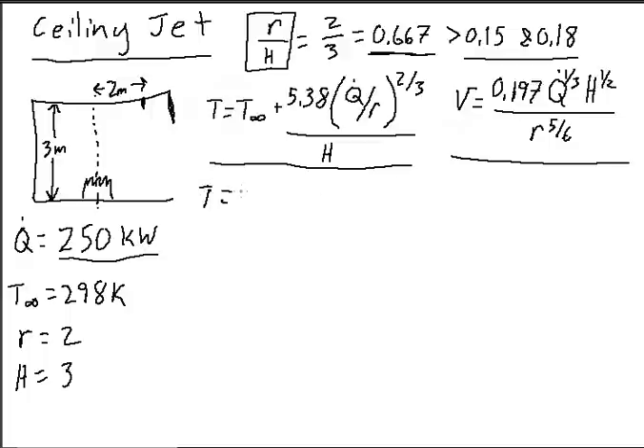So we can find temperature equals ambient temperature, 298, plus 5.38. Once again, this is an empirical constant, so it's important that we use the right units. If you're going to use different units, other than kilowatts and meters for the heat release rate and the radius, you can do that, but you'll need a different empirical constant.